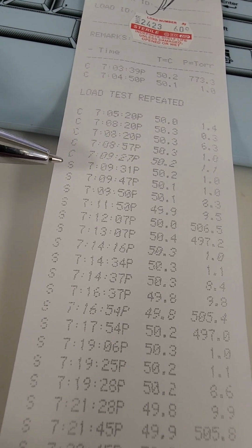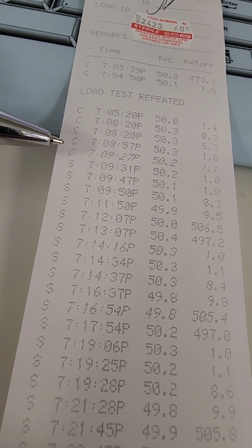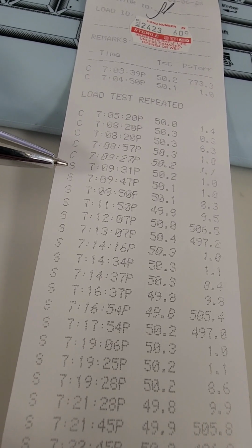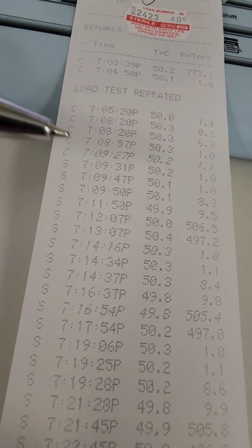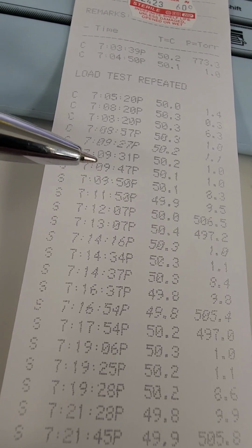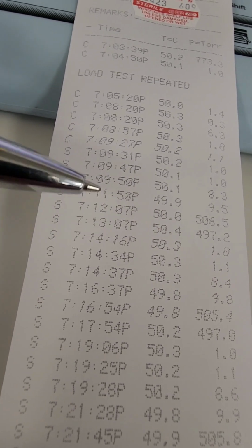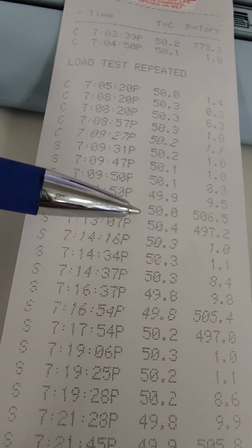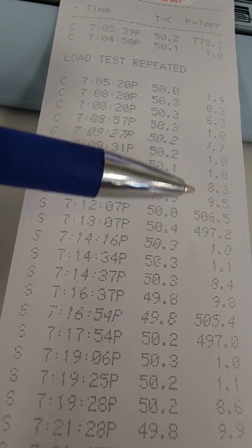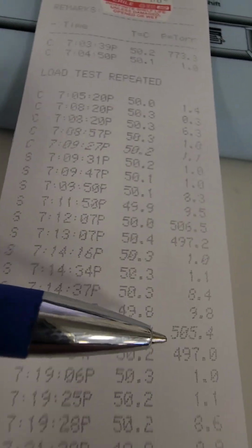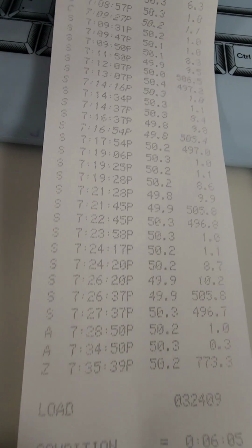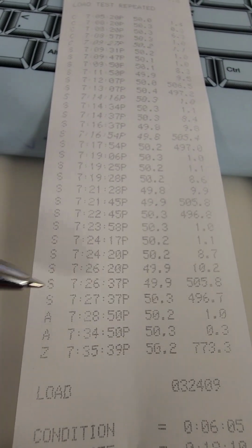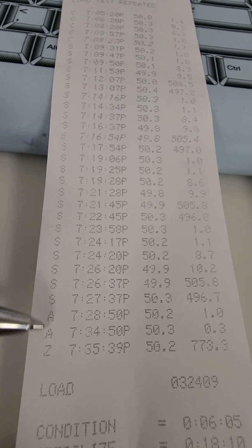And if it exceeds the ability of the unit, an abort will happen during the conditioning phase. Okay, so this shows you how much conditioning, and then the S stands for sterilization or exposure time. Depending on the unit, it'll be an S, or it'll say E, or it'll spell out exposure. Okay, that temperature is extremely important. And then you look at the pressure. Please be familiar with the pressure of your units and how many pulses in a cycle, because you can recognize if something's going wrong if that pressure's off.